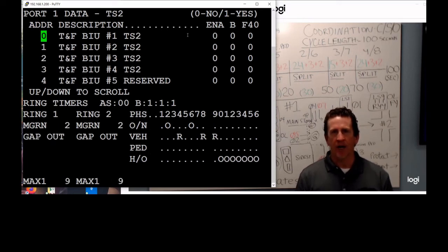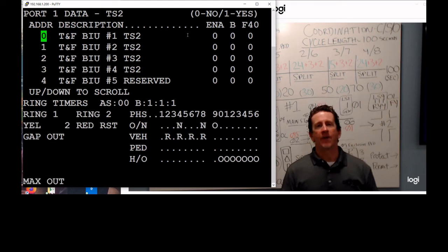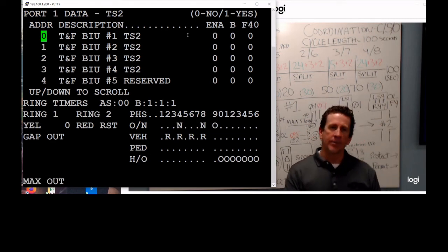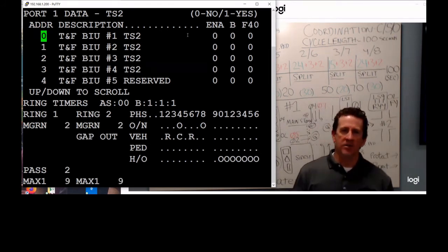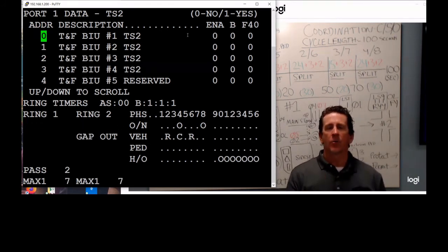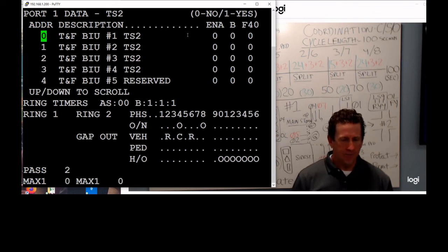The lower BIU does 9 through 12. If it's a 16 position back panel, the lower BIU does 9 through 16. So depending on where your failure is, if you have a failure on 1 through 8, we're going to be looking at that BIU number 1. If it's 9 or later, we're looking at BIU number 2. And that tells us, when we cover the alarm part, when we go into the frame faults, it associates and tells us a specific frame fault directed to that BIU.